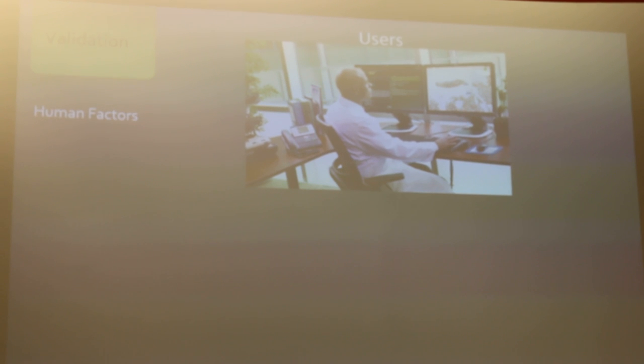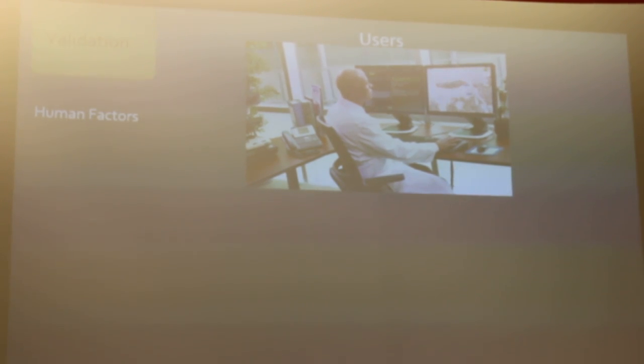Validation is just a little bit different — it's not set up to be a paper exercise. This is really getting our feelers out into our users and trying to see whether we built the right thing. A pathologist uses our device and does a diagnosis of tissue while having the case information up. When you do this sort of run, you're looking for a lot of different things. One is human factors — for example, if I'm building a large device with a hole just big enough for a finger, I want to make sure it doesn't chop that finger off, because users are going to do whatever users can do.